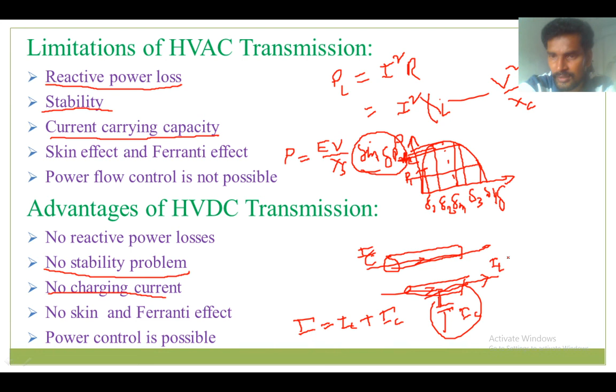Another concern is skin and Ferranti effect. In case of DC, the current is uniformly distributed throughout the conductor, whereas in case of AC, most of the current is confined to the skin depth of the conductor. Because of this, there will be some loss in the system. This is called skin effect. Ferranti effect: under lightly loaded or no load conditions, sometimes the receiving end voltage is more than the sending end voltage. That is called Ferranti effect. See, the skin and Ferranti effect will not occur in case of DC. Why? Because there is no frequency, and the current is uniformly distributed throughout the conductor. The Ferranti effect will also not be there in case of HVDC, because there is no charging effect in case of DC.